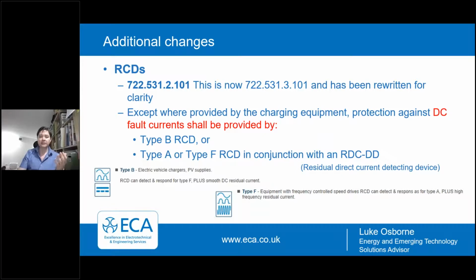These can be either a Type B RCD, which is built to tolerate DC noise and not become blinded by it, which is more and more apparent in many of our properties now due to the increasing amount of DC componentry that's installed and in use. So you can use a Type B RCD or a Type A or Type F RCD in conjunction with an RDC-DD. So what the hell is an RDC-DD? It's another long acronym, but it stands for the Residual Direct Current Detecting Device.